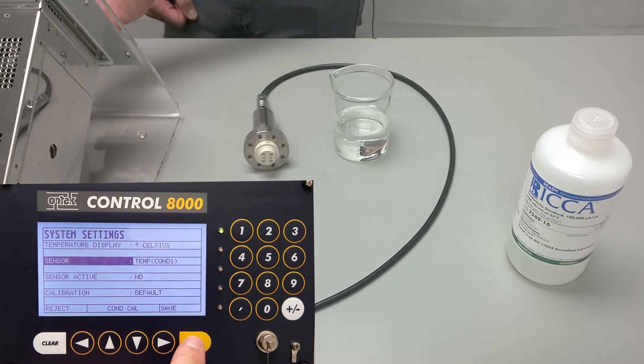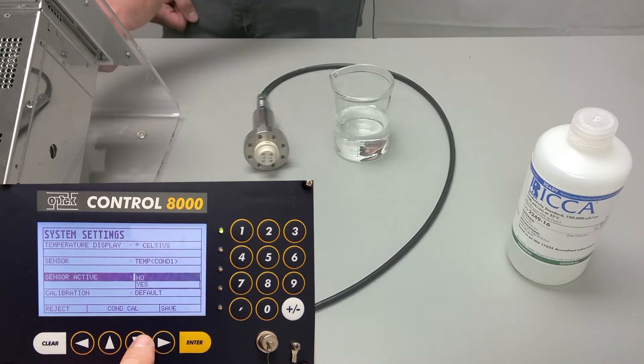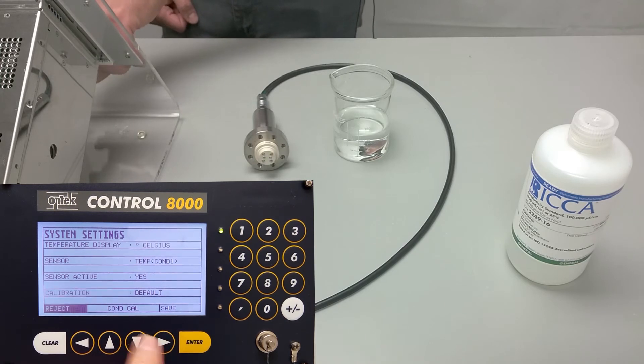We also want to ensure that COND1, which is the sensor we are calibrating, is the one that we have selected, and then scroll down to sensor active and change this to yes. Scroll down and press save.